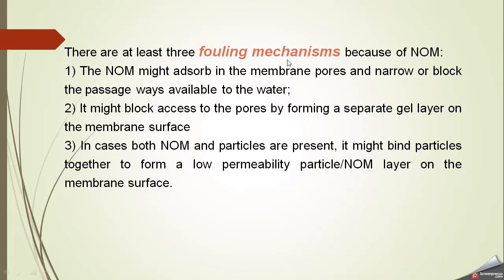There are at least three fouling mechanisms due to NOM. First, NOM may adsorb into membrane pores, narrowing or blocking the passageways available to water. At worst, it may block access to the pores by forming a gel layer on the membrane surface. If both NOM and particles are present, they may bind together to form a low-permeability combined layer on the membrane surface.